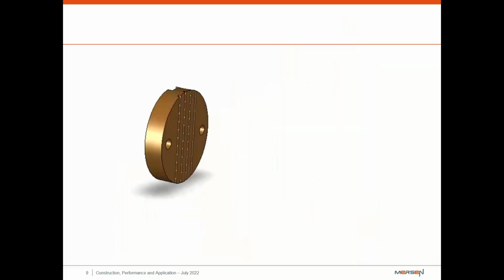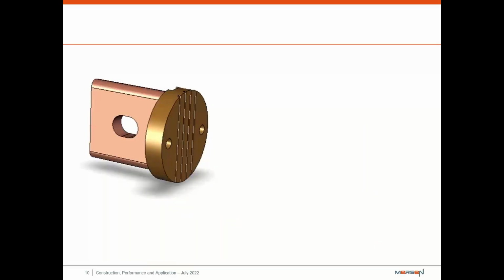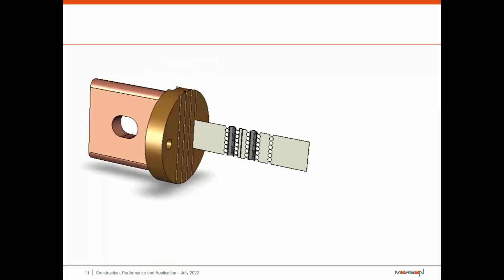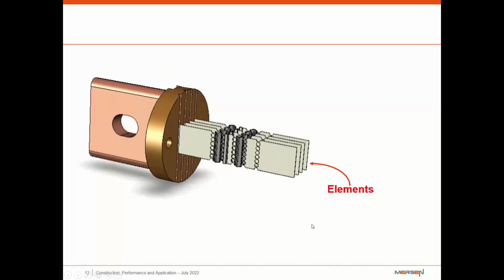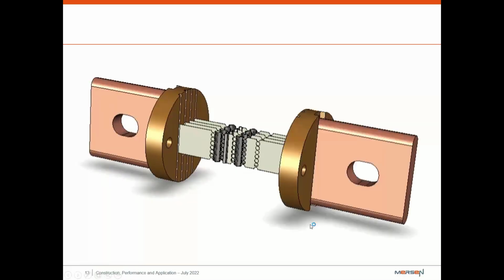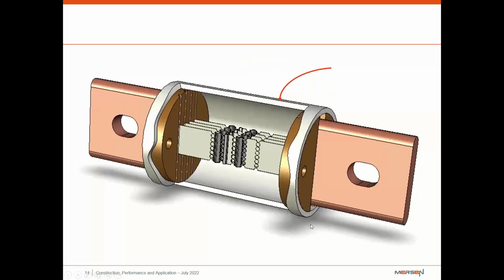So let's get into the actual construction of these fuses themselves. On one side, we're going to have our block. We're going to braze on our blade, and then inside we're going to have the element itself. This is where the magic happens. So if we want to have a 400 amp fuse and this is a 100 amp element, we're just going to put 4 of these elements in parallel. We'll have another braze block assembly on the other side, and then we'll put our body on it.